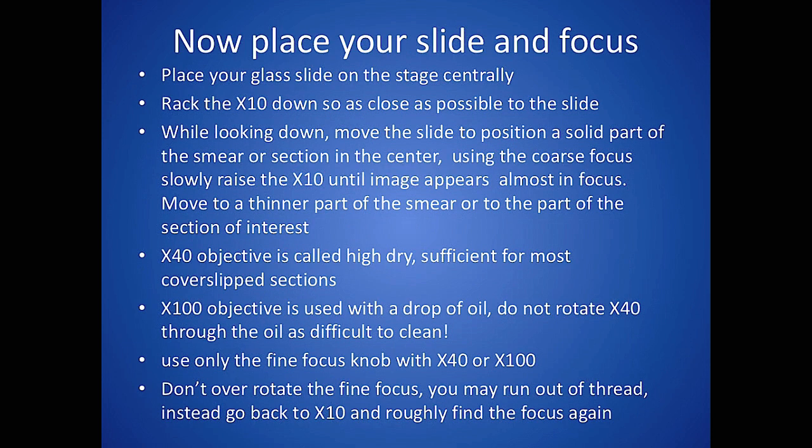Only use the fine focus knob when trying to sharpen your image with the 40x or 100x objective. If you use the coarse knob you could smash the slide. And don't over-rotate the fine focus if you're having trouble finding your image with 40x or 100x. The best thing to do is go back to your 10x and roughly find your focus again, rather than over-spinning and running out of thread on your fine focus.